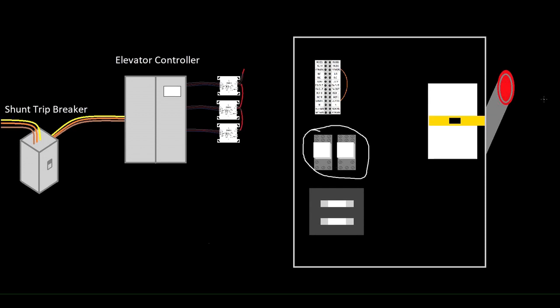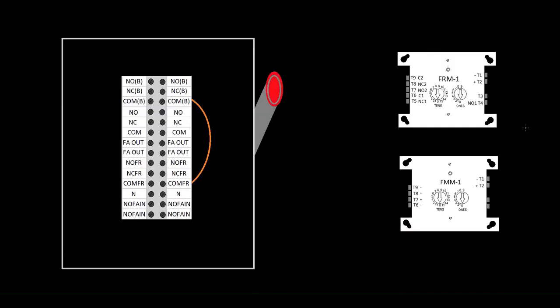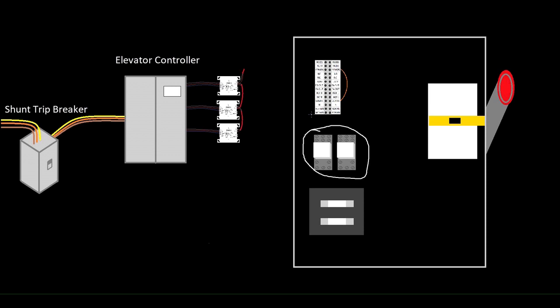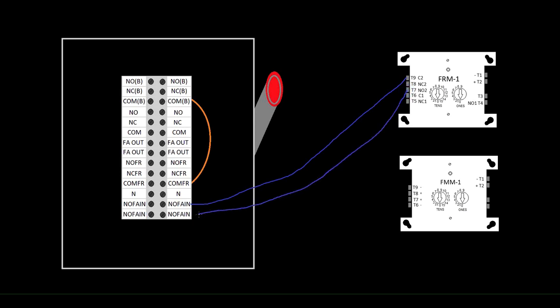We're going to scroll down and take a zoomed in look at just the terminal block here and I'll show you how this would get wired. Now obviously this doesn't take up as much space as it's showing here. Wiring this thing up is pretty simple. The first thing we're going to do is take our relay module, we're going to go common to NOFAIN, which stands for normally open fire alarm in. So normally open on our relay, and that part's done. So now the shunt trip portion of it is complete.